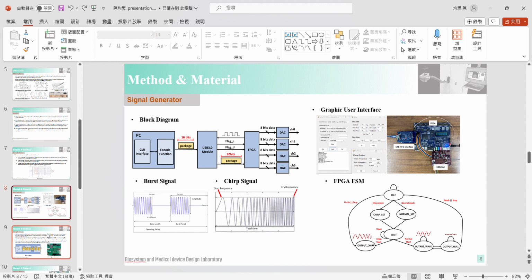The signal generation stage is structured as shown in the diagram. Users can select either burst mode or chirp mode through the graphic user interface, the GUI, that we have designed. In burst mode, a standard signal for focused ultrasound therapy can be configured with parameters including peak pressure, frequency, burst period, burst length, and the total duration. In chirp mode, users have the capability to quickly identify the central frequency of the ultrasound probe.